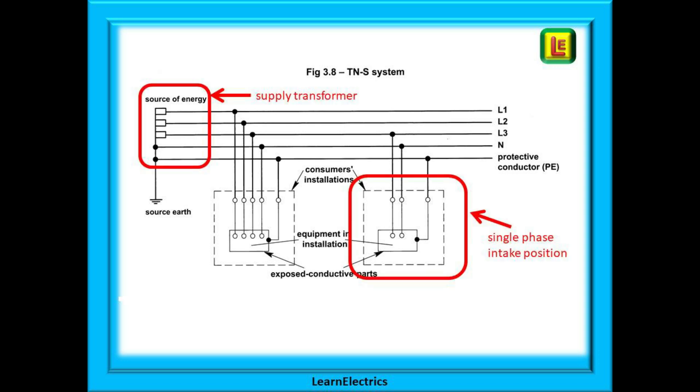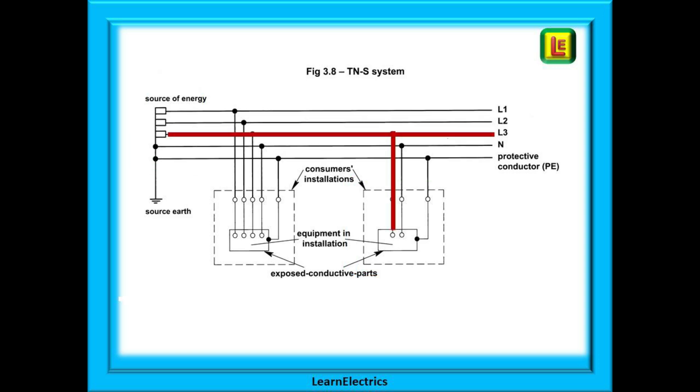Top left in the red box is the supply transformer. This is showing the three phases plus the neutral plus the earth. And at the bottom right we are boxed around a single phase intake position. To the left is a three phase intake position. And how is the wiring arranged for this single phase installation. We have used a brown wire here to mark the phase conductor. And blue for the neutral. With the green wire representing the earth conductor. This is a TNS system. So the earth and the neutral are separate throughout.